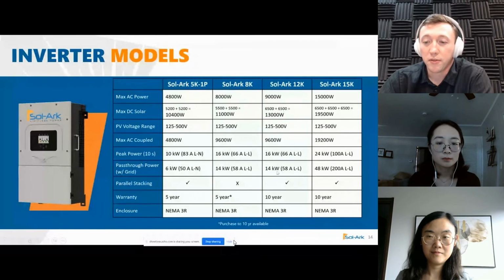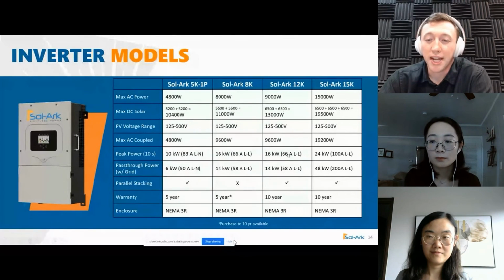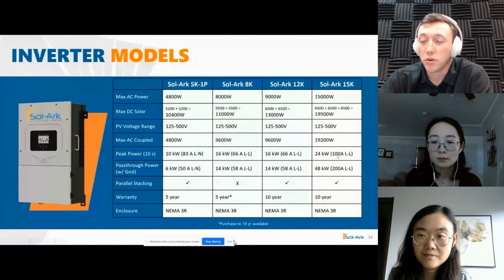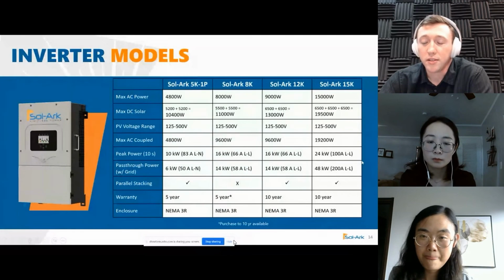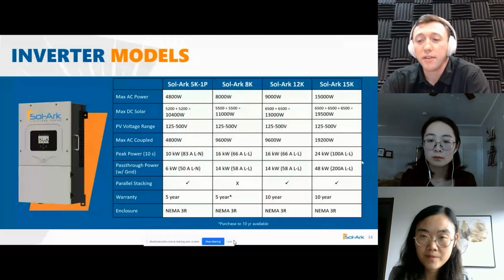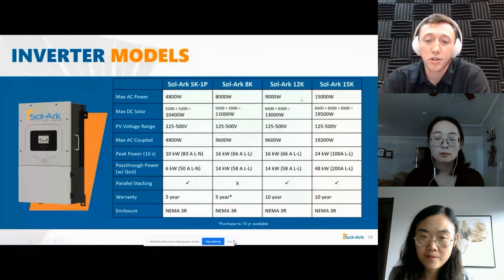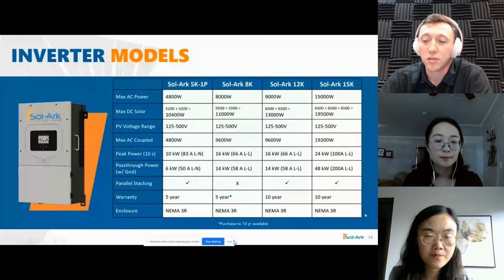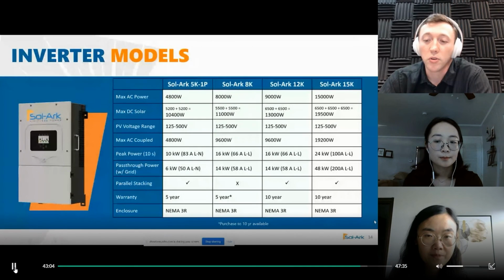Our peak powers are going to be different from each inverter here, but I'd like to touch on the 12K and the 15K. It has a 16 kilowatt surge for 10 seconds or a 24 kilowatt surge for 10 seconds on the Sol-Ark 15K. These surges really help with those larger appliances. For example, let's say you have a homeowner with a 3-ton or 5-ton AC that has a very large startup current. We're going to be able to provide that startup current for most models and provide power to the home so it doesn't throw the inverter into a fault.